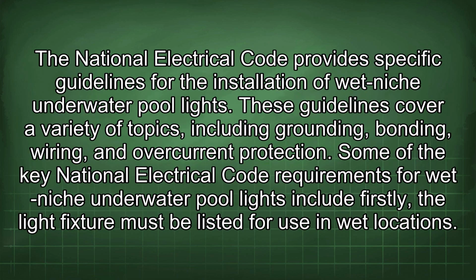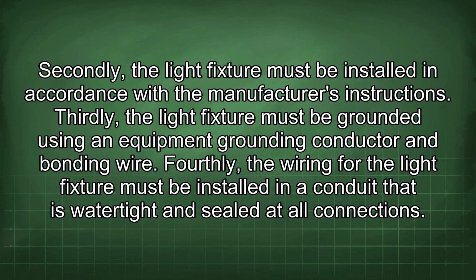The National Electrical Code provides specific guidelines for the installation of wet niche underwater pool lights. These guidelines cover a variety of topics, including grounding, bonding, wiring, and overcurrent protection. Some of the key National Electrical Code requirements for wet niche underwater pool lights include: firstly, the light fixture must be listed for use in wet locations. Secondly, the light fixture must be installed in accordance with the manufacturer's instructions. Thirdly, the light fixture must be grounded using an equipment grounding conductor and bonding wire.